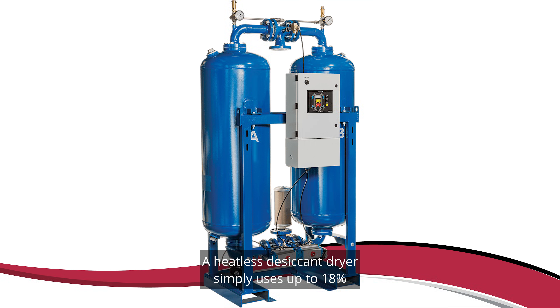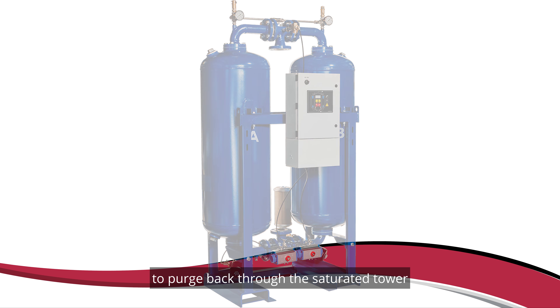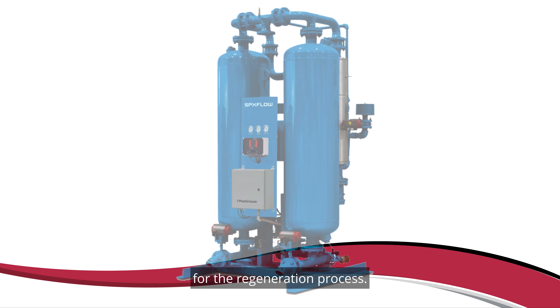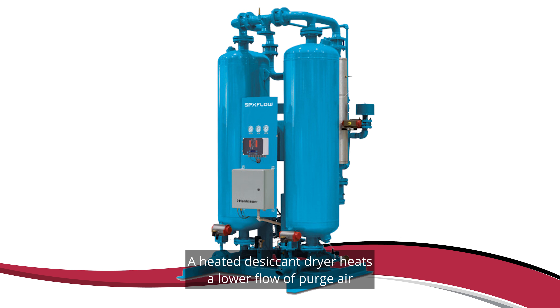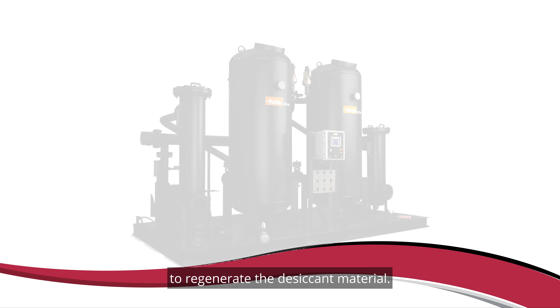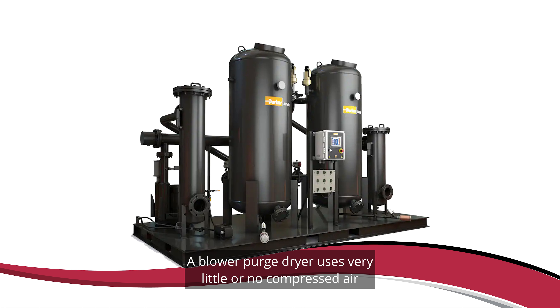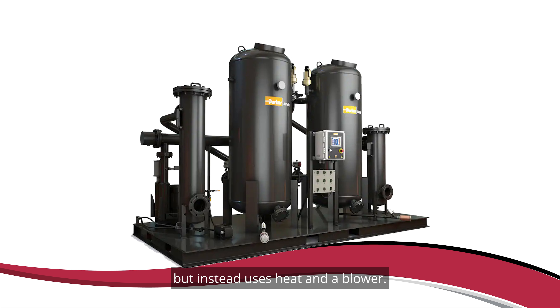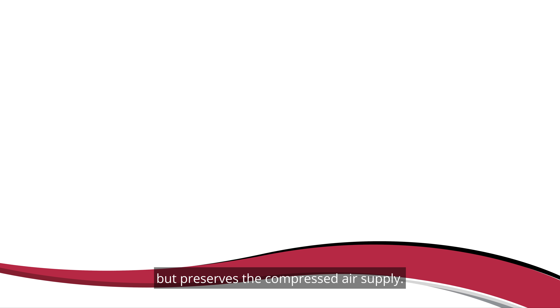A heatless desiccant dryer simply uses up to 18 percent of the rated capacity of the dryer to purge back through the saturated tower for the regeneration process. A heated desiccant dryer heats a lower flow of purge air to regenerate the desiccant material. A blower purge dryer uses very little or no compressed air in the regeneration process, but instead uses heat and a blower. It takes more energy to operate, but preserves the compressed air supply.